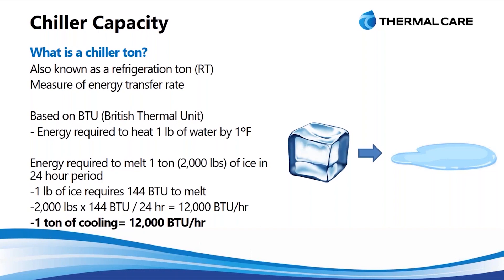Many people I've met over the years who have been in the business for a long time didn't actually know the foundation of this. It comes from a British thermal unit, a BTU — that's a measurement of energy to heat one pound of water one degree Fahrenheit. To get to the chiller ton, we look at 2,000 pounds of ice and how much energy it takes to melt that completely in 24 hours, which works out to about 12,000 BTUs per hour. That's what we call a chiller ton.